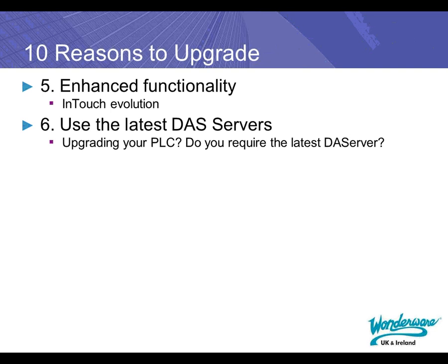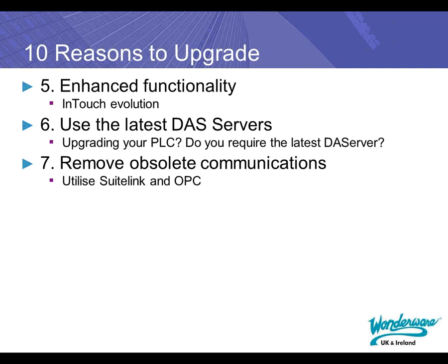You can use the latest DA servers. In order to communicate to the latest PLCs, you will require the later DA servers. These newer DA servers may not always be compatible with older versions of InTouch, and indeed your I/O server license may actually not license the later DA servers. Also, to look at removing obsolete communications, older versions relied on BDE to communicate. This now is obsolete and has been replaced by OPC and SuiteLink.